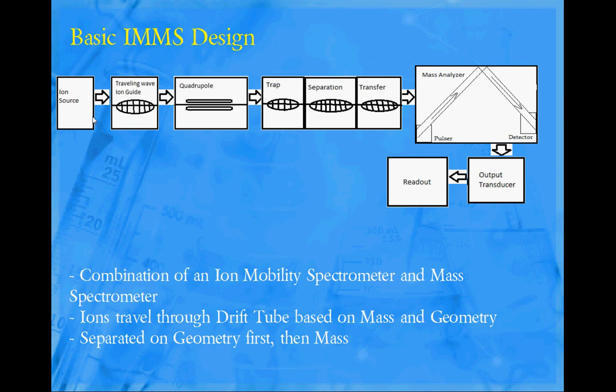The mass analyzer is somewhat different than what a normal mass spec looks like. This uses a pulser that incorporates the exact same potential energy into every single ion, regardless of their mass. And they go through the exact same length of drift tube, so the only difference is their mass. And that detector is going to receive the different masses at different times based on their weight. The lighter ones are going to come off sooner because they have more kinetic energy. You can just use the kinetic energy equation, it's very simple math, to determine the actual mass of each ion.